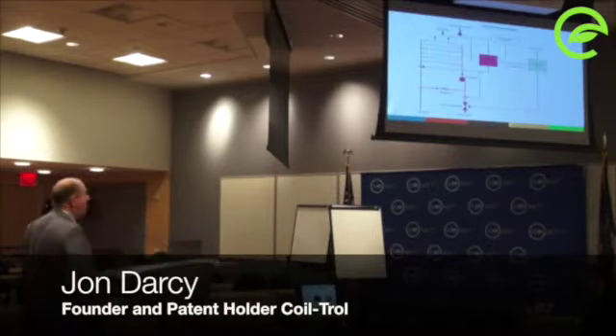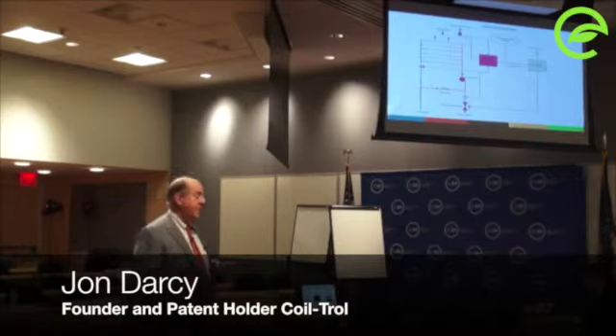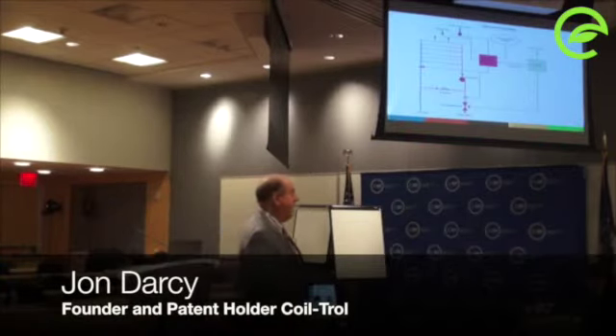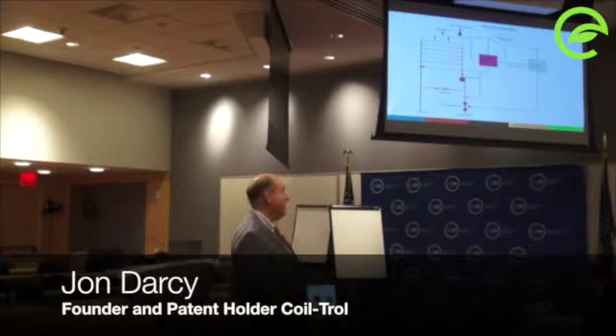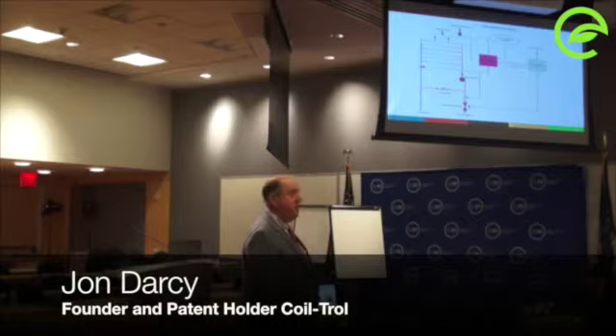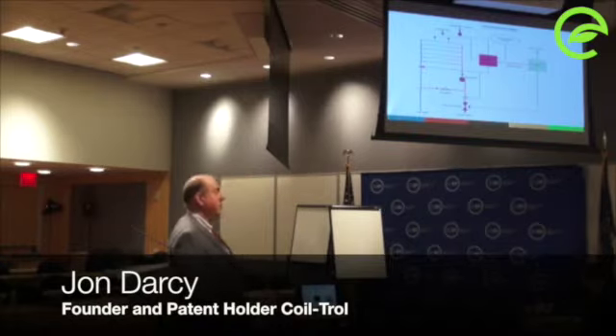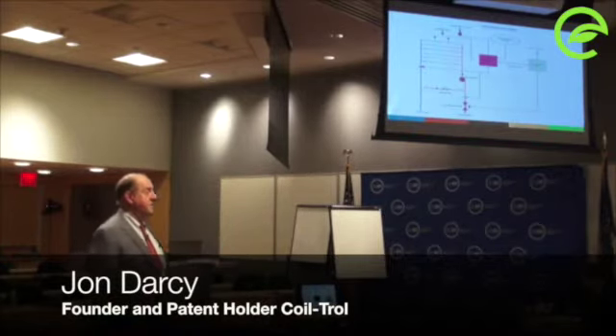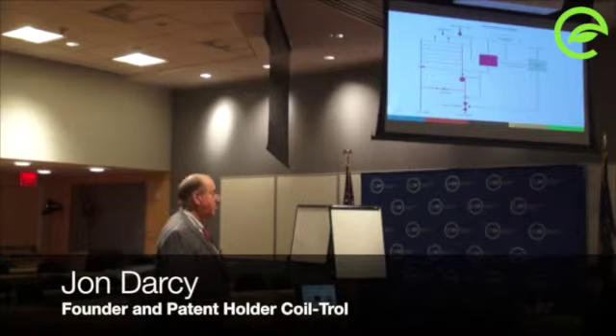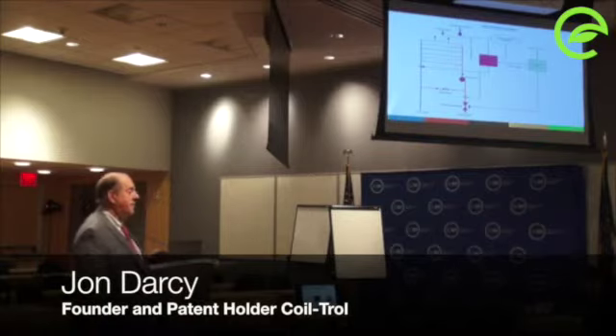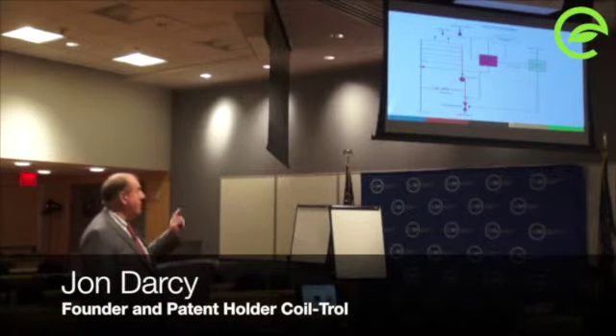You can probably do a whole building, if you have 6 air handlers or 8 air handlers, for less than $100,000. And your payback on it, on a million square foot building, you're probably using $800,000 to $1 million worth of cooling energy, and the savings on the chilled water pump is very substantial.